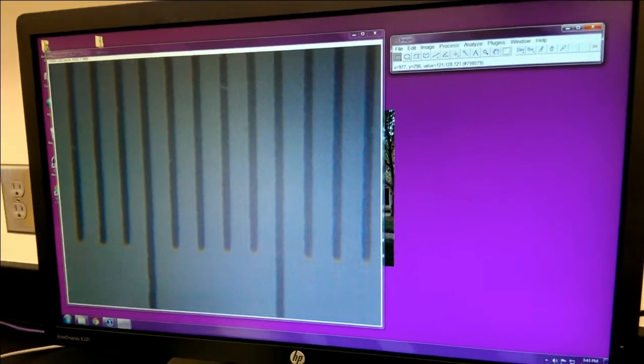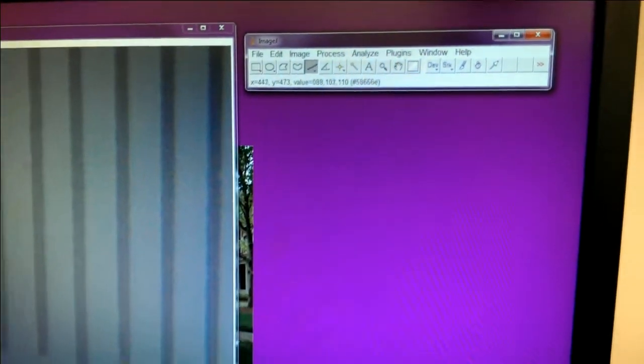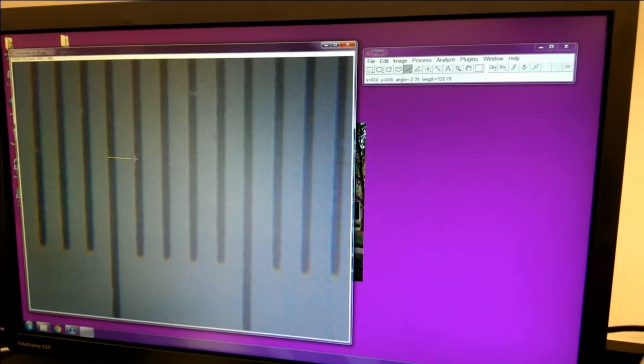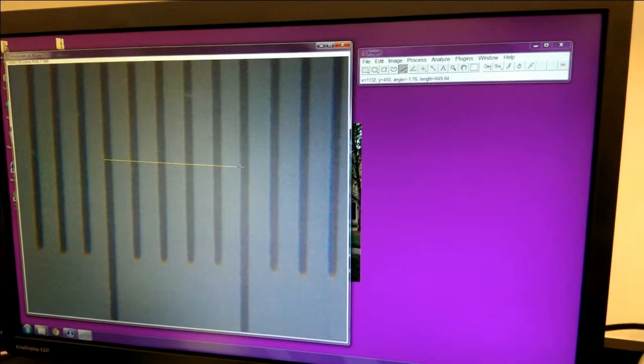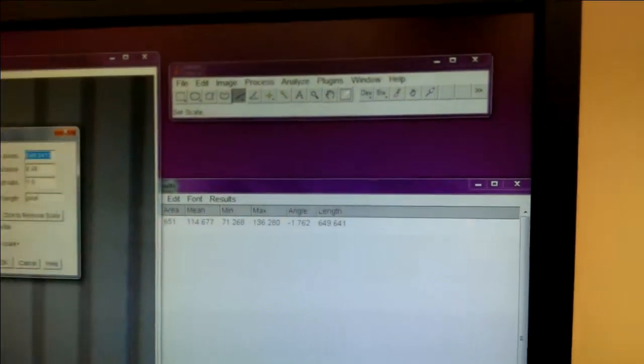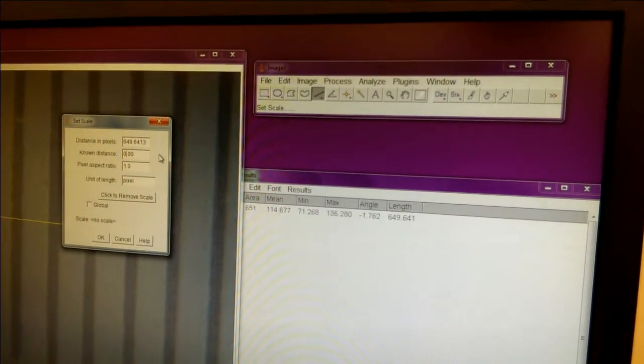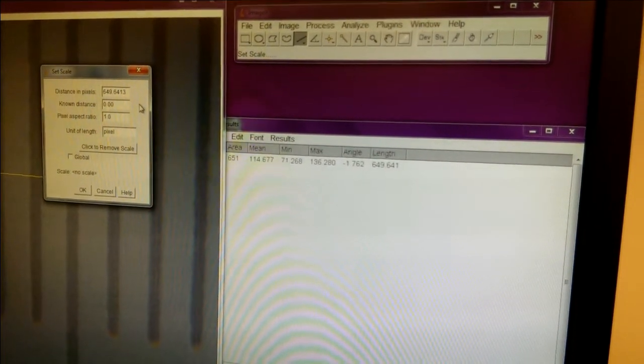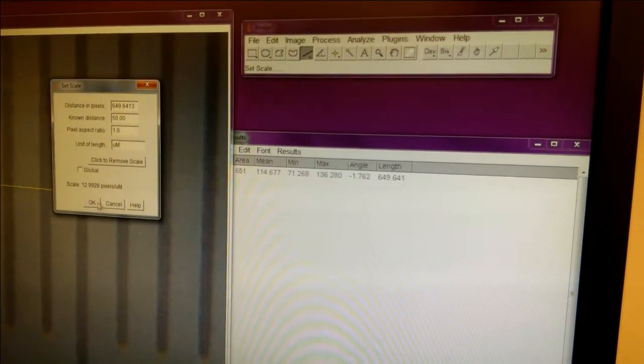So what you can do is draw a line crossing some of these little hash marks, where each hash mark is 10 microns wide. So you want to go up to the menu where there's a straight line tool, and click on that, and then come back over to your image, and for instance you can select 5 bars. So pick either from the left, or center, or right, and start drawing across. So that's 1, 2, 3, 4, 5. And I haven't drawn it perfectly horizontally, I've tried to draw it orthogonal to the lines. So now, if you go to Set Scale, it actually automatically puts that distance here. So now you need to put the known distance. I've used 5 lines, and each one has a spacing of 10 microns, so that's going to be 50. And then unit of length, microns, you can do U, M. Okay.